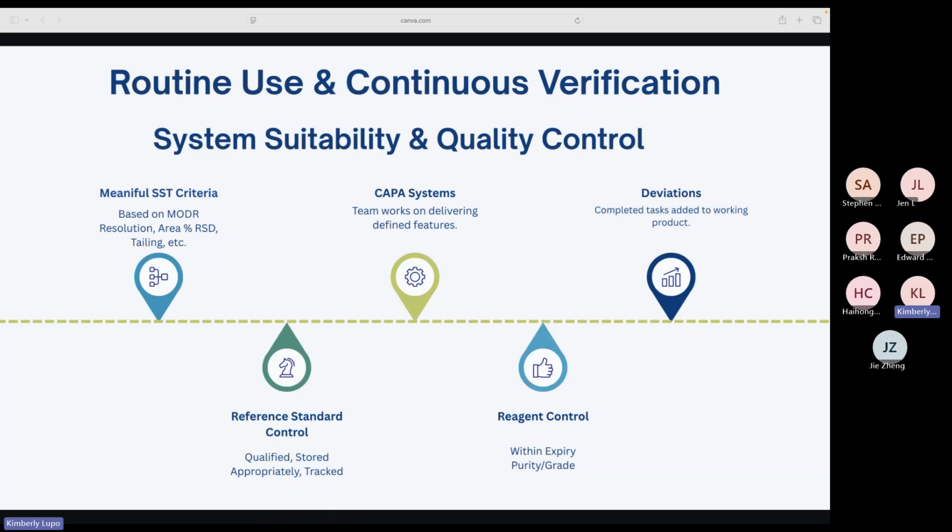The key is having clear criteria in your quality system for what constitutes major versus minor. Every deviation, even minor ones, needs to be documented. For major deviations or recurring patterns of minor deviations, your CAPA should include a root cause analysis. Pay attention to patterns. One deviation is an incident, 3 similar deviations in 3 months is a trend, 5 deviations across multiple methods involving the same equipment is a systemic issue. Sometimes a pattern of deviations is telling you that the method itself is a problem. It's too complex, too sensitive to small variations, not robust enough for routine use.